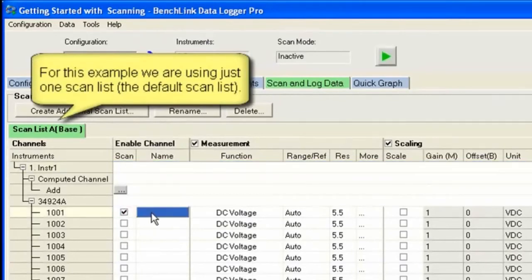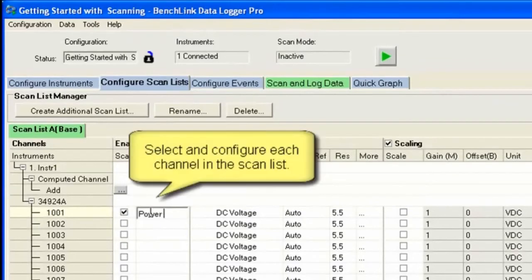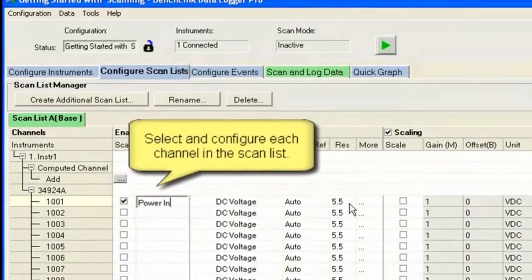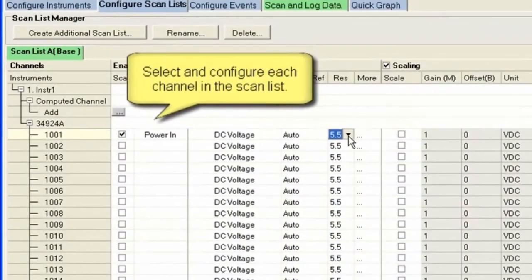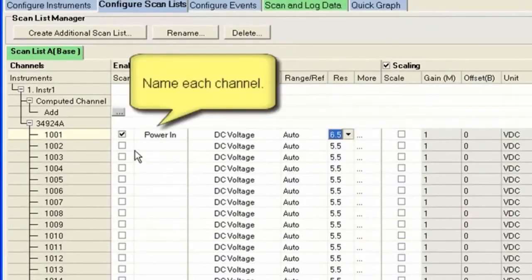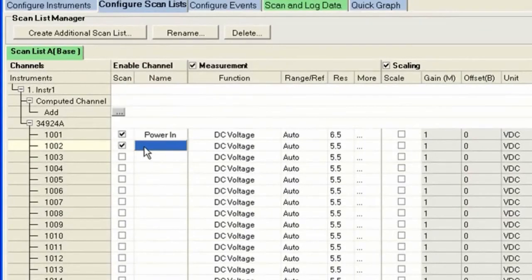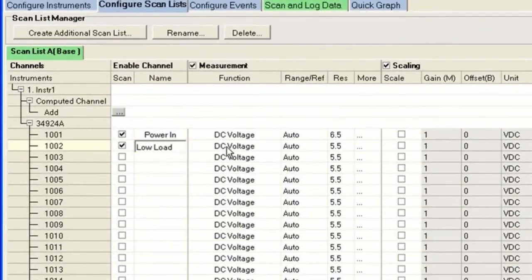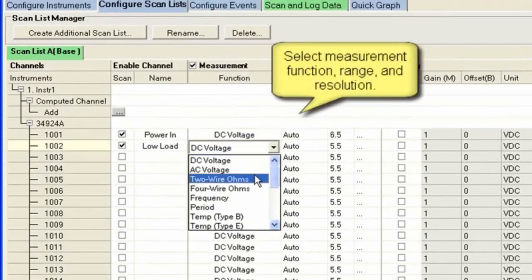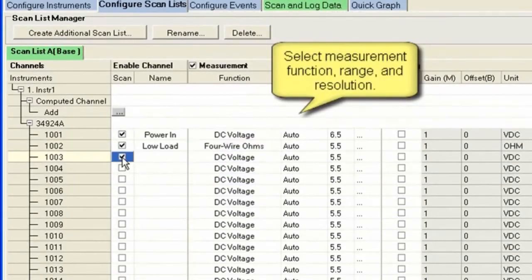I'm going to start configuring five different scans. In the first one I'm going to look at the power in, which is a DC voltage. I actually want to look at it with a lot of accuracy, so I'm going to go to six and a half digits. On channel two, I'm going to look at a fairly low resistance load. So to make the best possible measurement there, I'm going to want to go to four wire ohms to compensate for any lead resistance I may have.